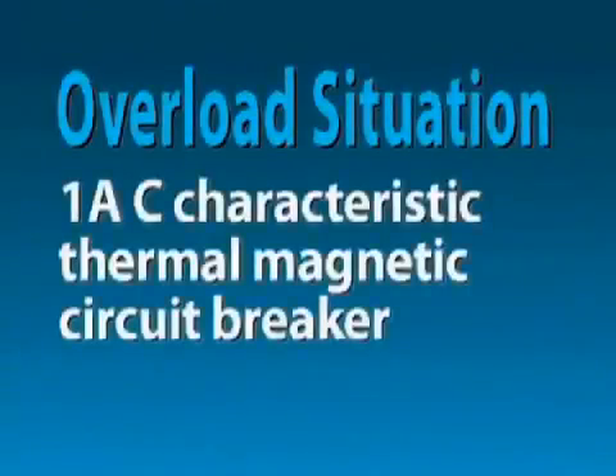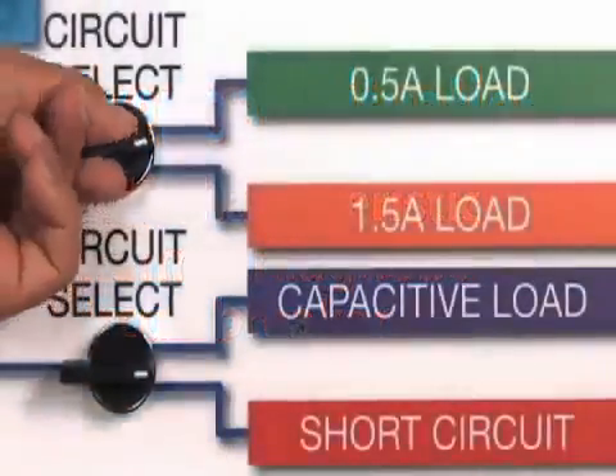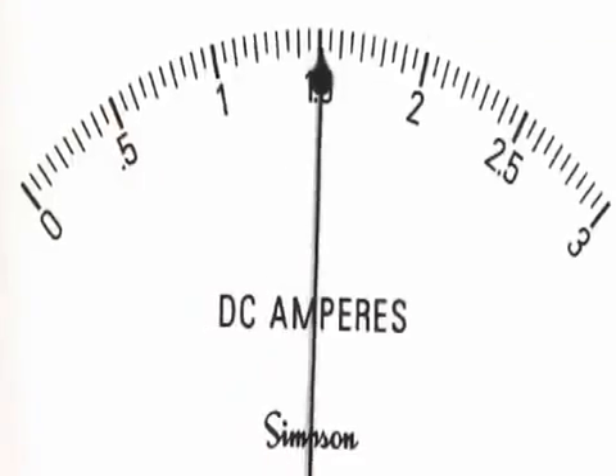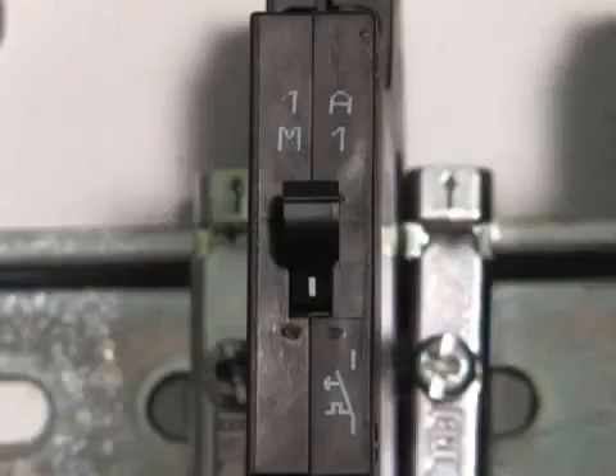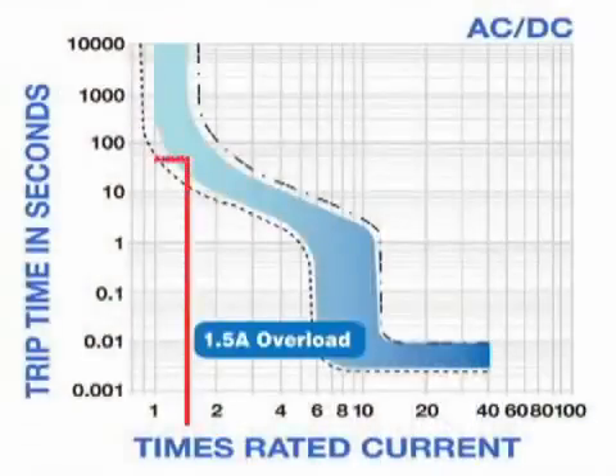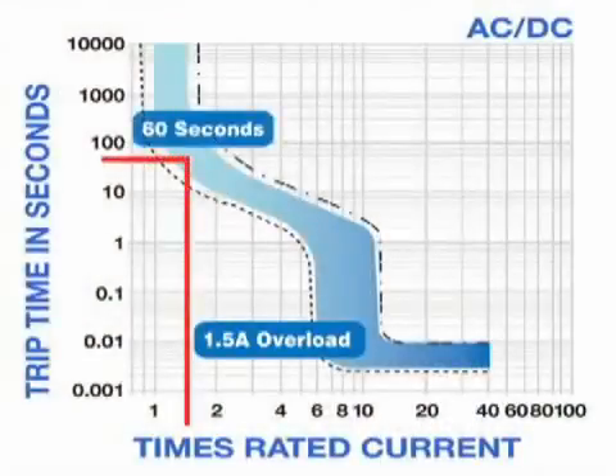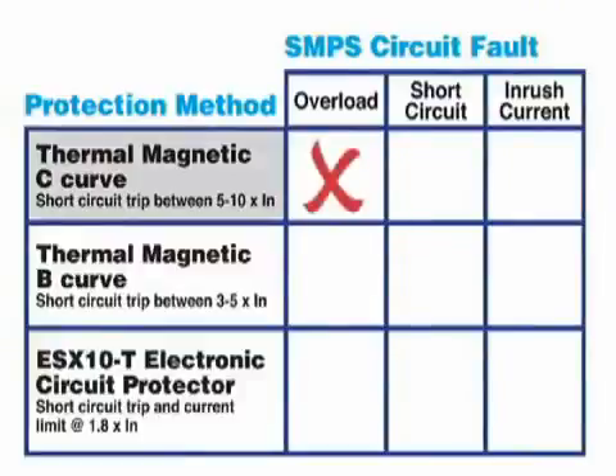Our first situation is an overload. We'll demonstrate an overload situation with a 1 amp C characteristic thermal magnetic circuit breaker protecting the load. Notice the amperage is now at 1.5 amps. There is an overload situation of 500 milliamps, and the breaker has not tripped and will not trip for approximately 1 minute. This is not desirable protection for sensitive 24-volt DC circuits.